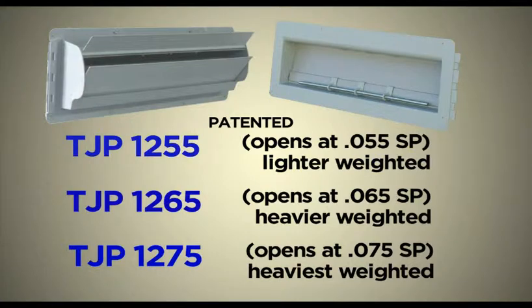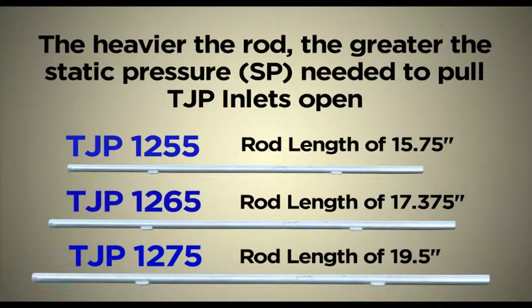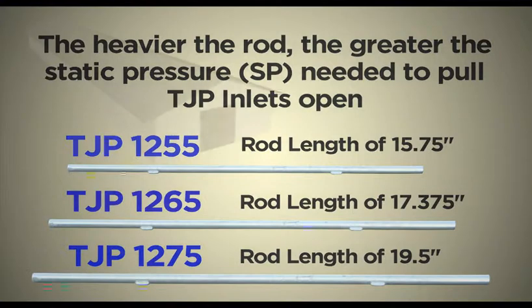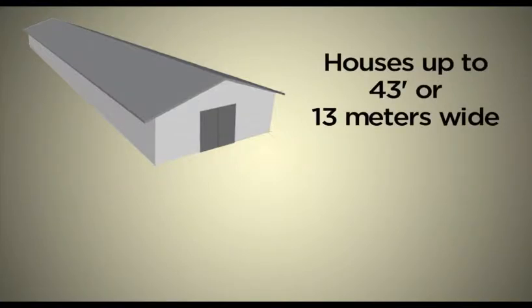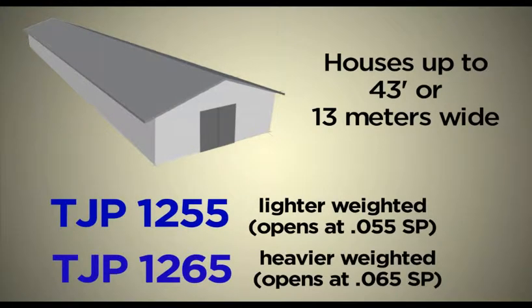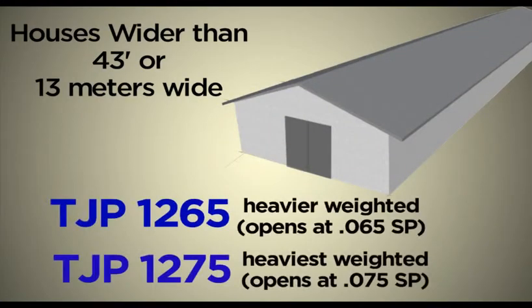You have three choices of TJP inlets: the TJP 1255, lighter weighted; the TJP 1265, heavier weighted; and the TJP 1275, heaviest weighted. The heavier the rod, the greater the static pressure needed to pull TJP inlets open. In houses up to 43 feet or 13 meters wide, use a combination of TJP 1255, lighter weighted, and TJP 1265, heavier weighted. In houses wider than 43 feet or 13 meters, use a combination of TJP 1265, heavier weighted, and TJP 1275, heaviest weighted.